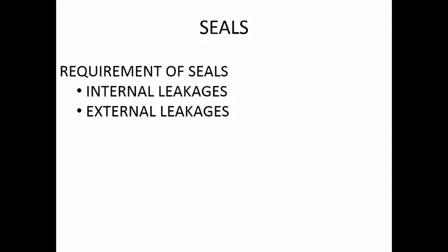Even though we don't want any kind of leakages, whether internal leakages or external leakages, we are employing the seals, but seals will not prevent 100% leakage. They will go up to say 99.99% or something, but there is always going to be some amount of leakage. This leakage is needed to create the lubrication of the system.